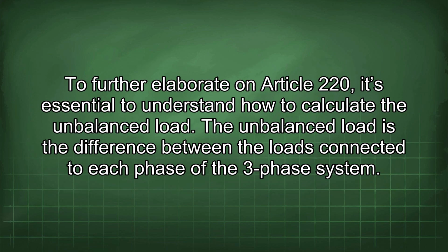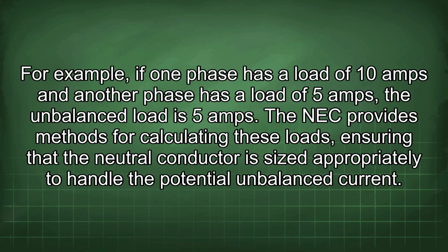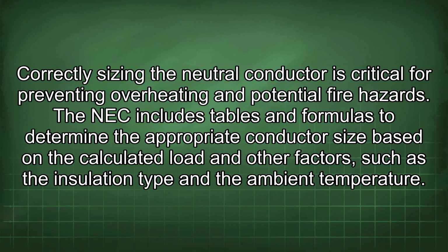To further elaborate on Article 220, it's essential to understand how to calculate the unbalanced load. The unbalanced load is the difference between the loads connected to each phase of the 3-phase system. For example, if one phase has a load of 10 amps and another phase has a load of 5 amps, the unbalanced load is 5 amps. The NEC provides methods for calculating these loads, ensuring that the neutral conductor is sized appropriately to handle the potential unbalanced current. Correctly sizing the neutral conductor is critical for preventing overheating and potential fire hazards. The NEC includes tables and formulas to determine the appropriate conductor size based on calculated load and other factors, such as the insulation type and the ambient temperature.